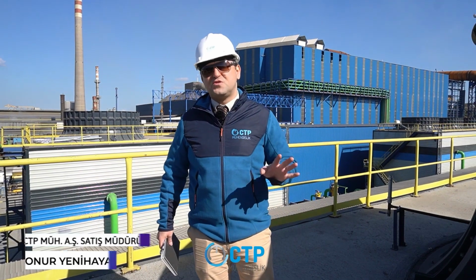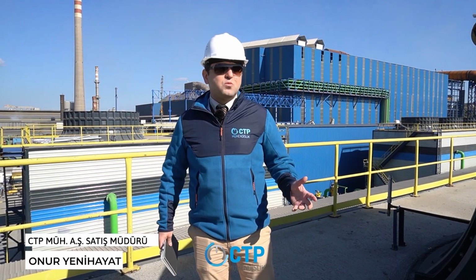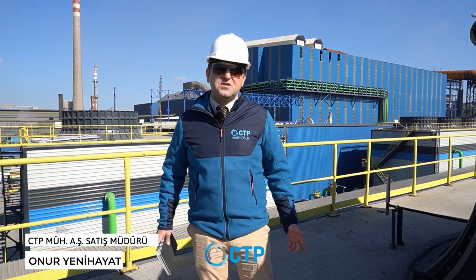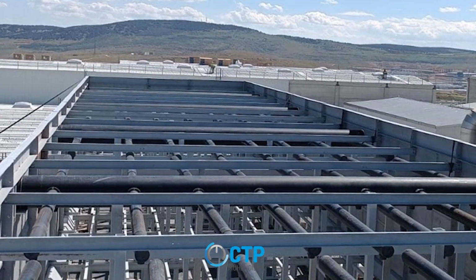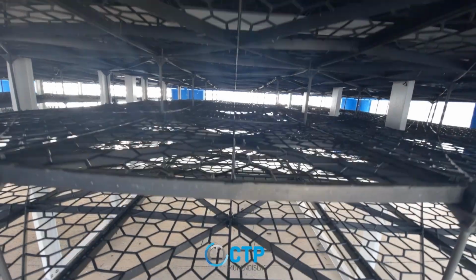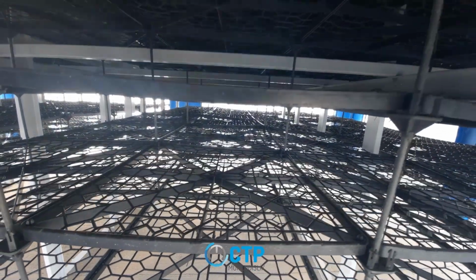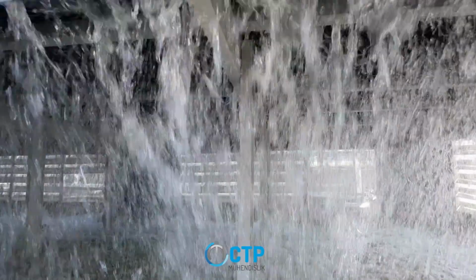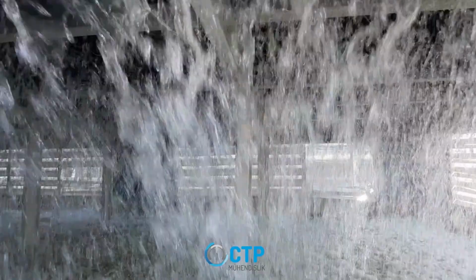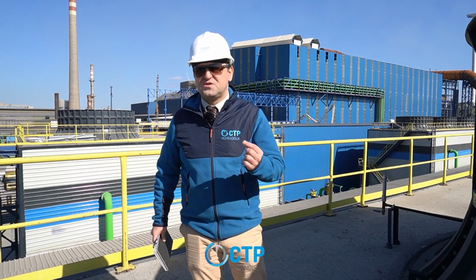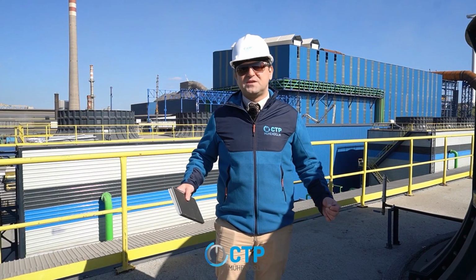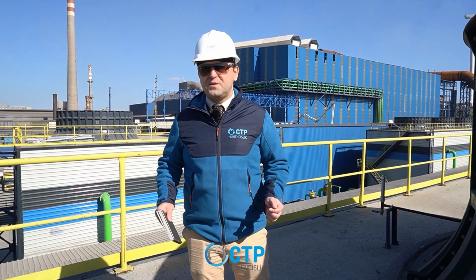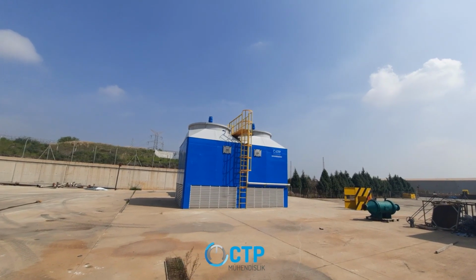This cycle continues endlessly. Now, the way that a cooling tower works is actually quite simple. There is a water distribution system, and beneath this water distribution system, there is fill material. The water distribution system pulverizes the water, achieving a state of near perfection. It breaks it up into very tiny particles, so small they can hardly be called droplets, and sprays them onto the fill. The purpose of the fill is to slow down the flow of water.